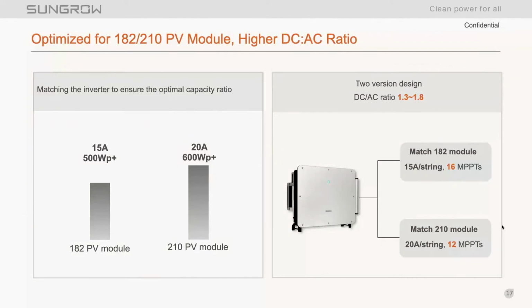We talked at the top of the presentation about the inverter being optimized for the 182 210 millimeter wafer PV module that's coming out, or is already out, and we're starting to see in more and more projects. The challenge with these is that with the inverters that are on the market right now, our max input short circuit current doesn't really allow for a very high DC to AC ratio. Sometimes depending on the module selection and the string size, based on the geography and the square footage that we have to work with on certain projects, we're not really able to achieve a very high DC to AC ratio.